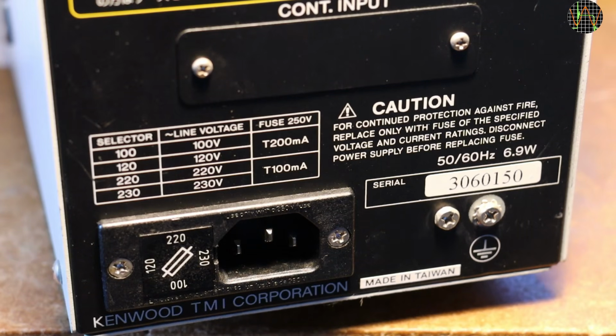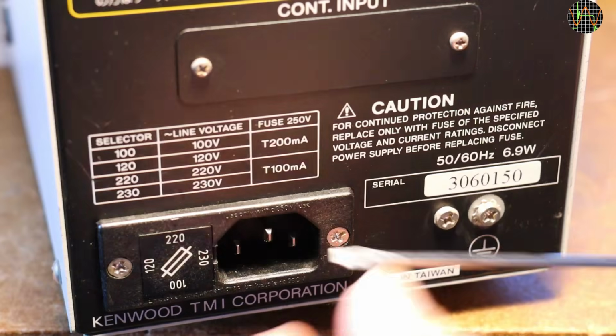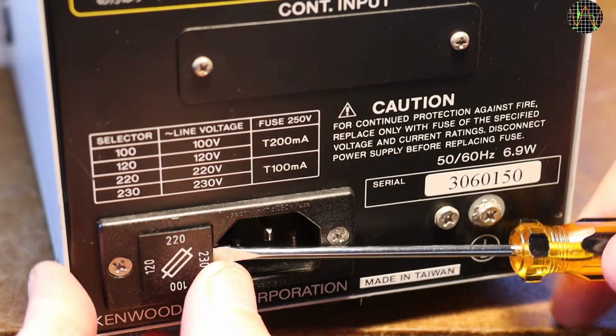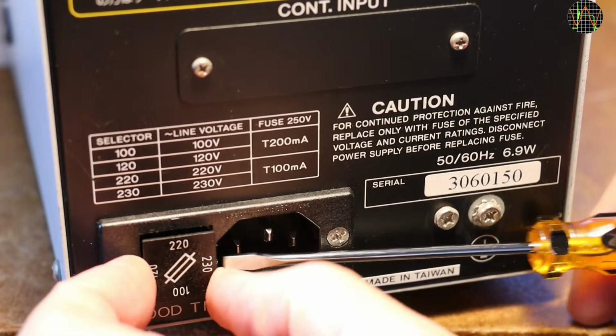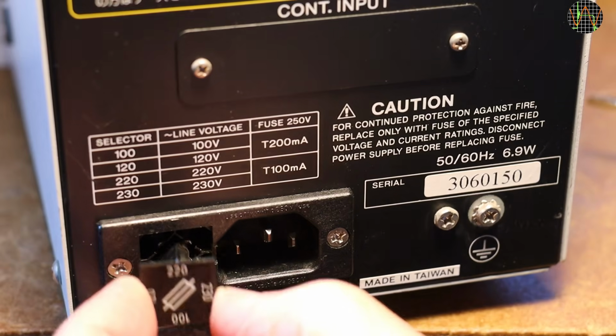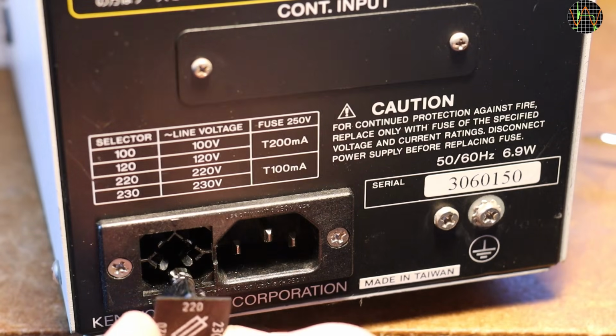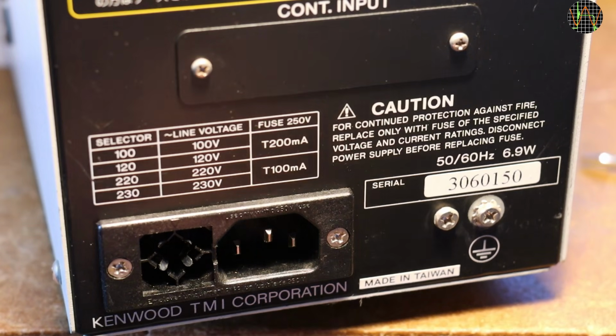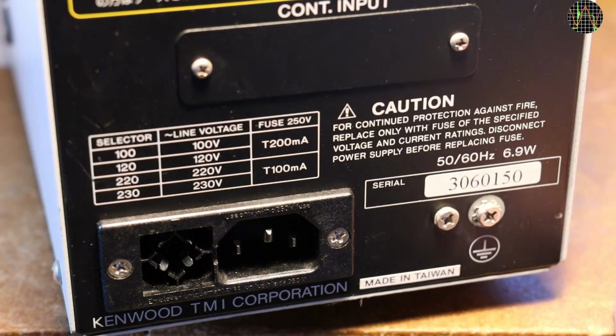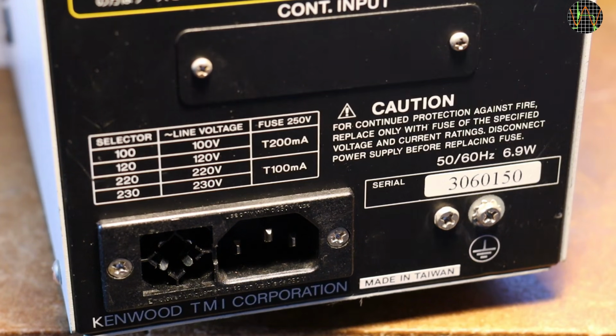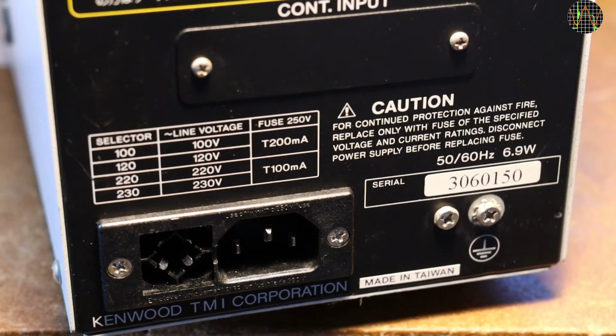For the selector here, I assume the voltage you can read, that is, it's not upside down or sideways, is the one selected. That would be 220 volts, but the UK has 230 volts, which can rise up to 250, so this setting should be changed. I mean, it's not a big problem, and I assume the previous owner has used this in the UK for ages, but it's less stressful for the unit if the voltage is set correctly.